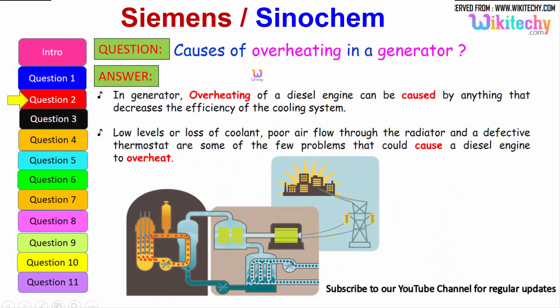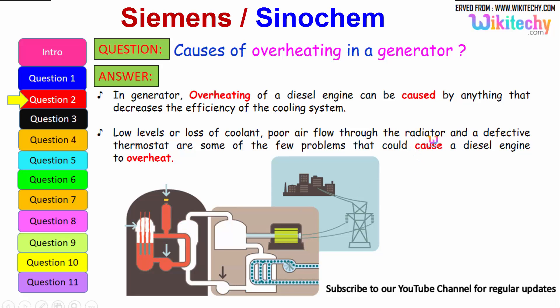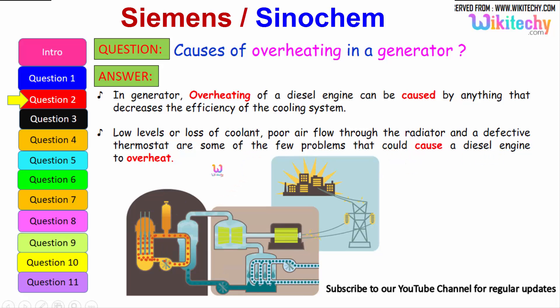Let us move on to the next question: causes of overheating in a generator. Overheating of a diesel engine can be caused by anything that decreases the efficiency of the cooling system. It can be due to the loss of coolant or low levels of coolant, poor airflow through the radiators, and a defective thermostat — some of the problems that could cause a diesel engine or generator to overheat.